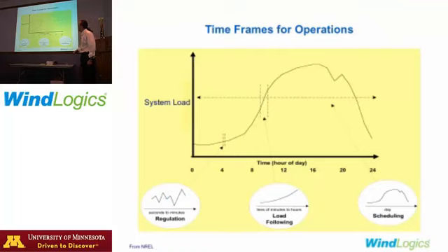Of course, I think you're familiar, I'll talk here about regulation, which is the reserve service, the ancillary service for just the next few seconds or minutes. And then load following will often be like a 5-minute time step of how we dispatch our units to the change. And then the scheduling day ahead is usually an hour by hour sort of day ahead plan, right? How you run a power system.